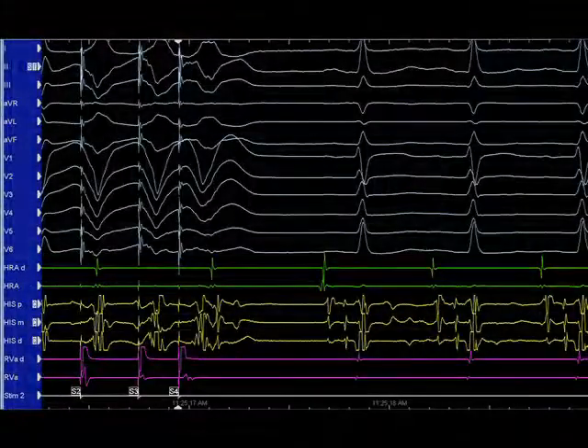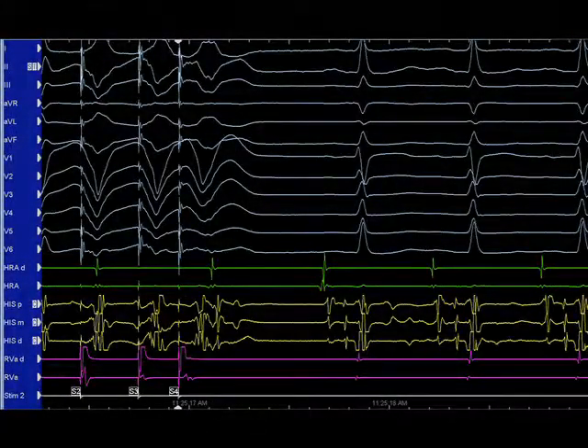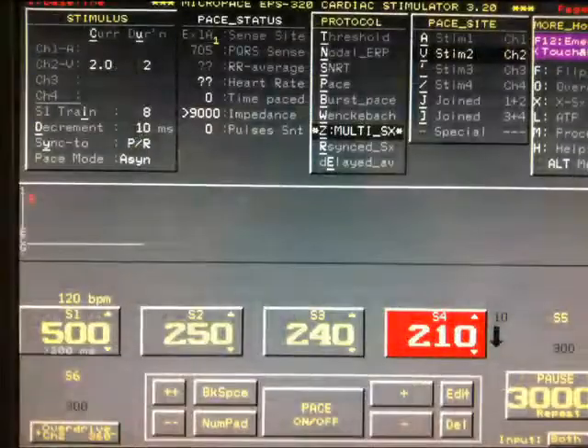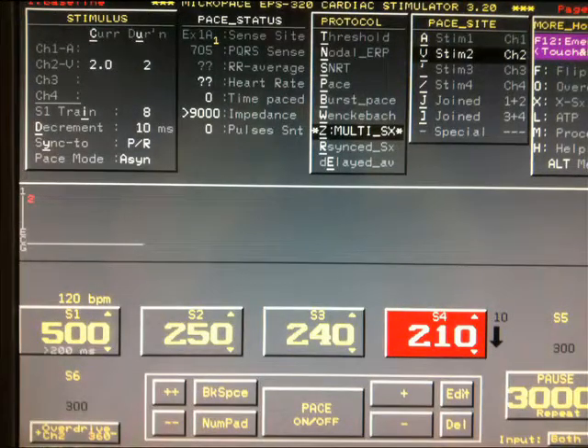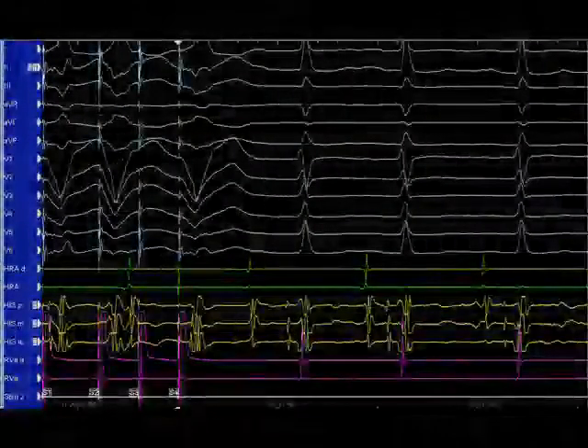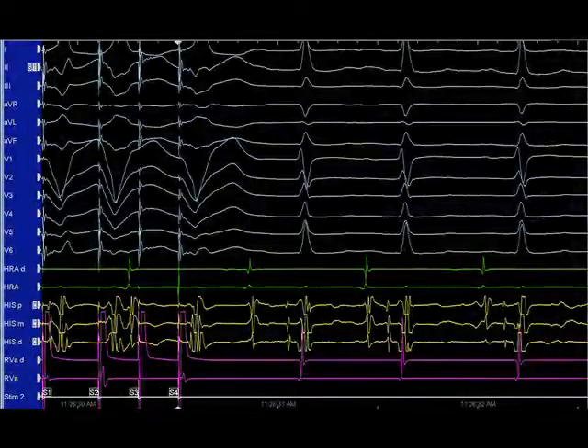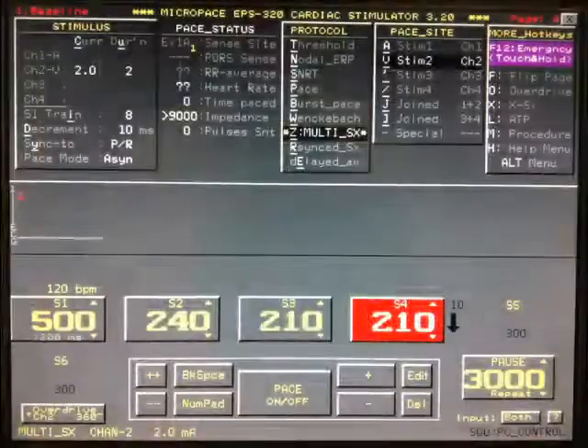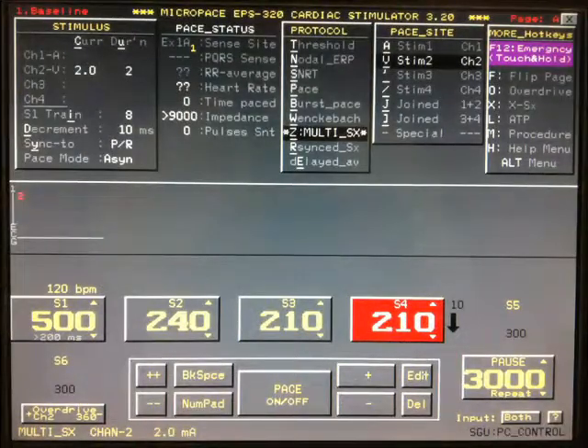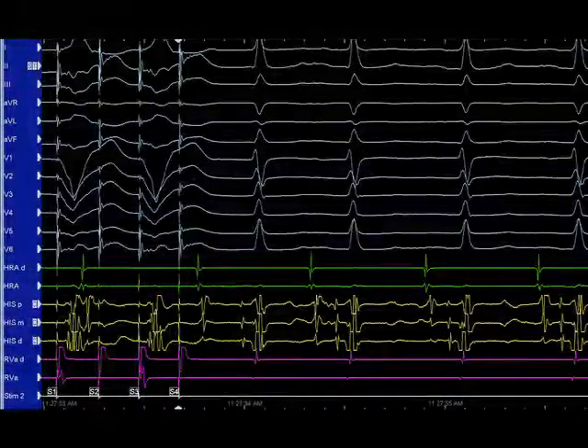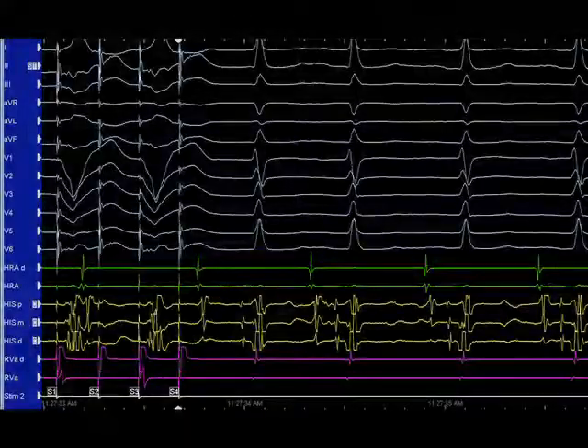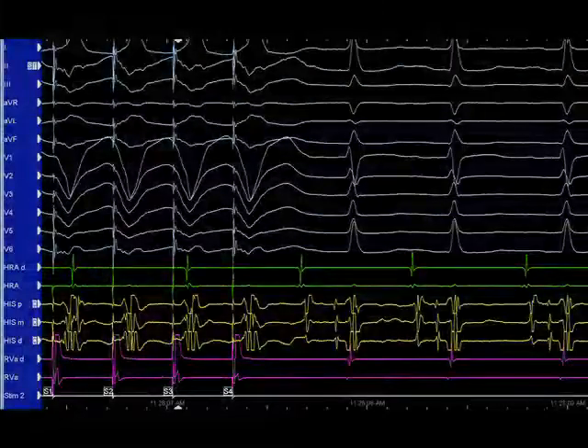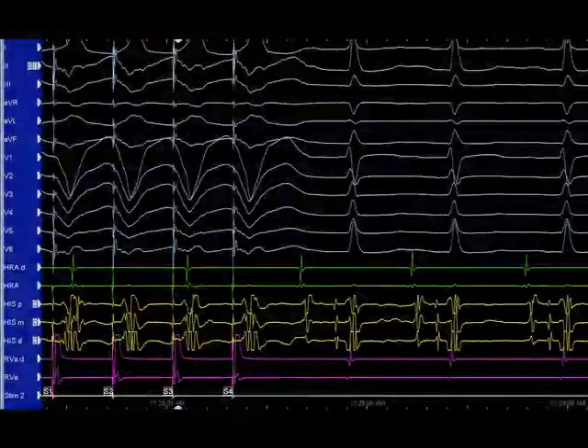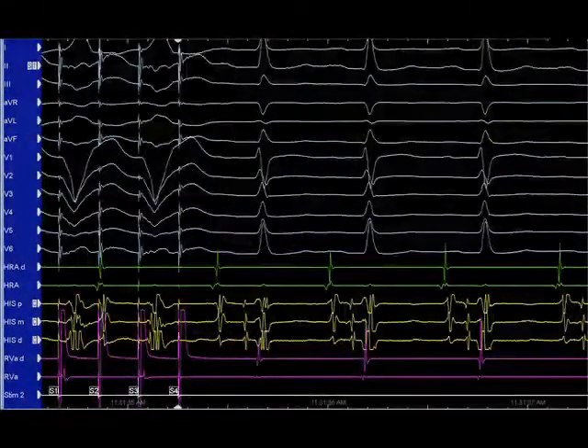The third extra stimulus, or S4, is decreased by 10 milliseconds until loss of capture, or the lower limit is reached. At that point, the S4 is increased by 10 milliseconds and S3 is decreased by 10 milliseconds. The process of decreasing extra stimuli is completed until S3 loses capture, and the S4 decreased by 10 millisecond increments. The process of decreasing the extra stimuli continues until S2 loses capture. Triple extra stimuli are repeated with the second drive train of 400 milliseconds until S2 loses capture.